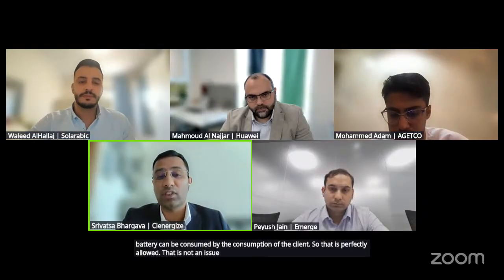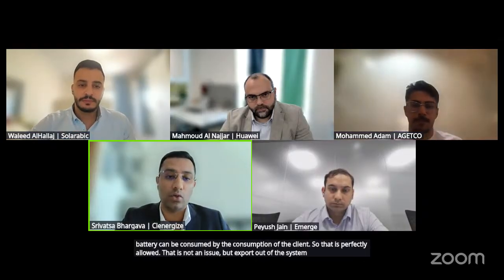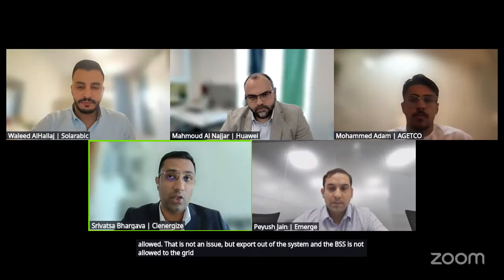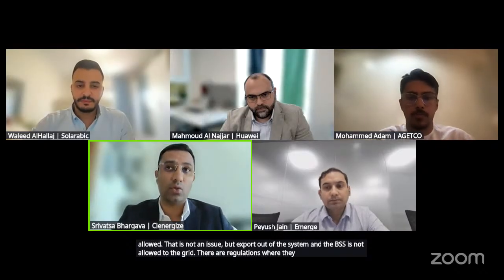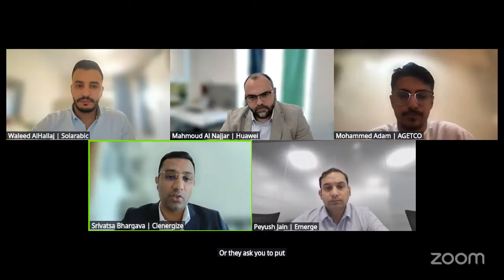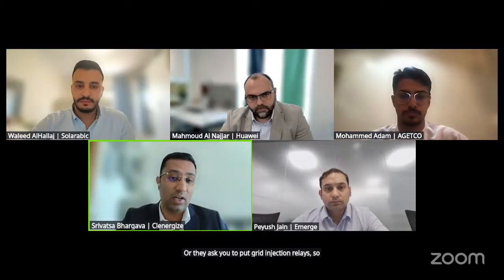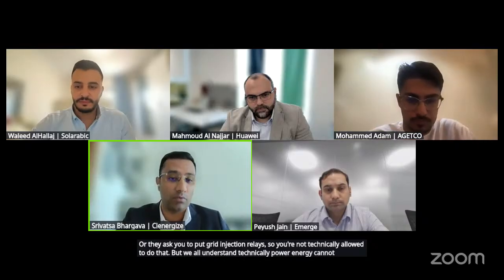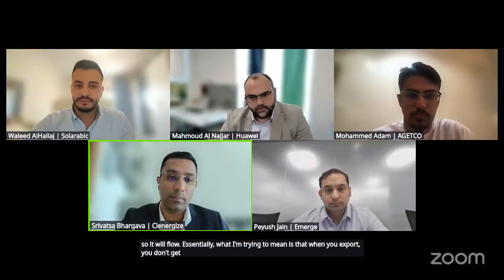But export out of the system and the BSS is not allowed to the grid. There are regulations where they allow or they ask you to put grid injection relays. So you're not technically allowed to do that. But we all understand technically power energy cannot be stopped, so it will flow. Essentially, what I'm trying to mean is that when you export, you don't get any benefit out of it.